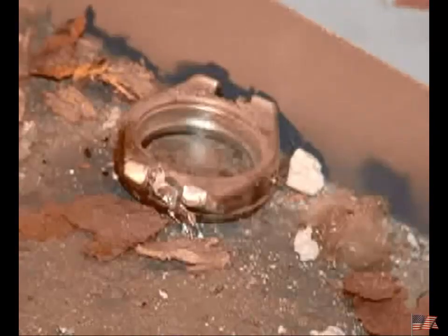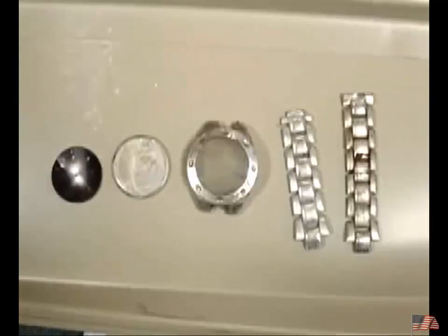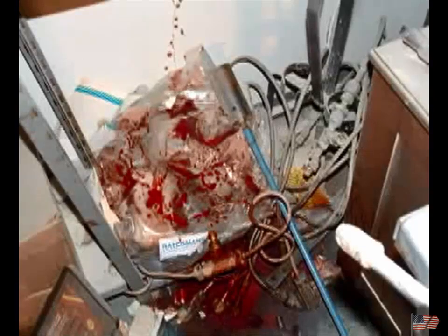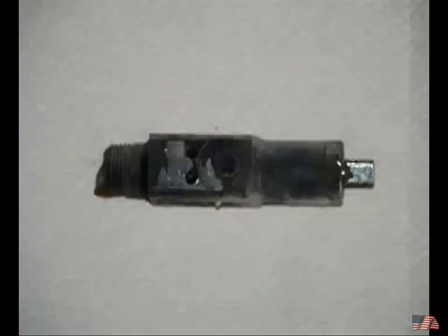You can see the workbench is pretty much damaged here, and this item on the workbench just happens to be the gentleman's watch that was ripped completely off his arm, and his arm was severed completely between the elbow and the wrist. This is where his severed arm landed, and this is a picture of where the cylinder valve and cylinder landed. A close-up of the cylinder valve shows the markings of where the adjustable wrench was on the valve.